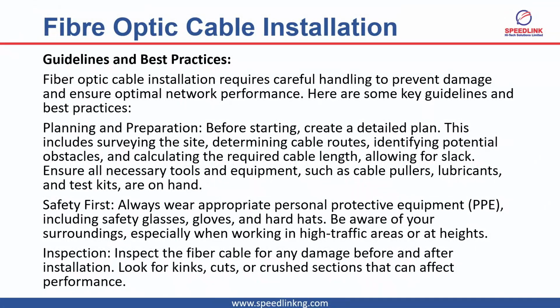You'll not be running a new cable and somewhere in the cable, one side is bent like an L, right? As you see something like that, you just know that this cable is damaged at this point. There's no need straightening the cable again, because for it to be bent that way, it must have broken a core inside it. So at that point, you know that this cable is not good, so that you don't go and run something that you have to pull again and start from the beginning. Imagine running a kilometer of cable and at 500 meters, there's a damage. You start thinking of cut and join or removing the whole cable and starting afresh again. It would be a bad thing.